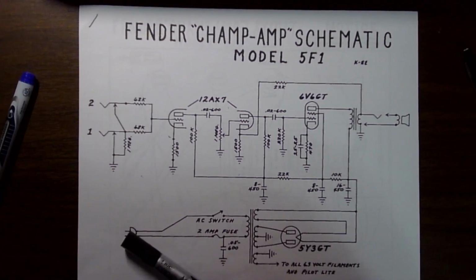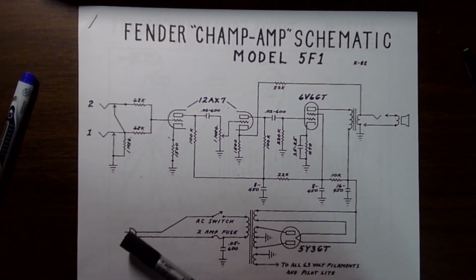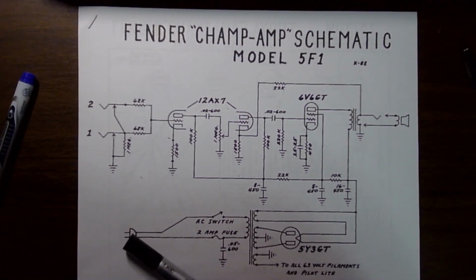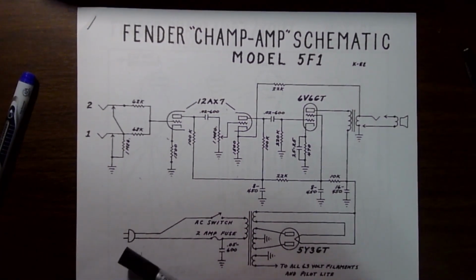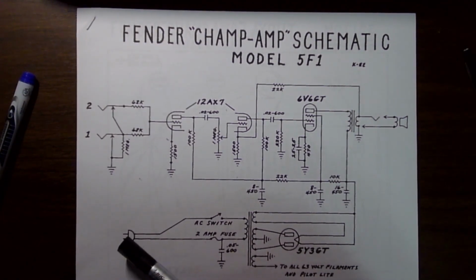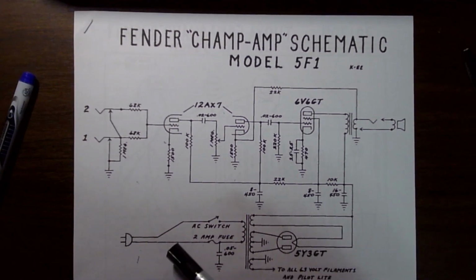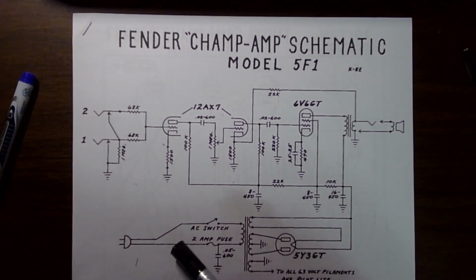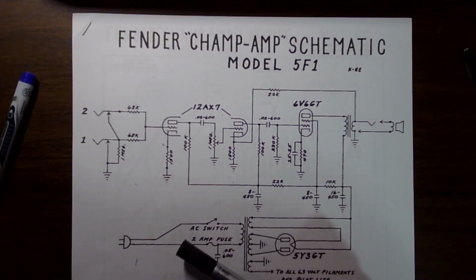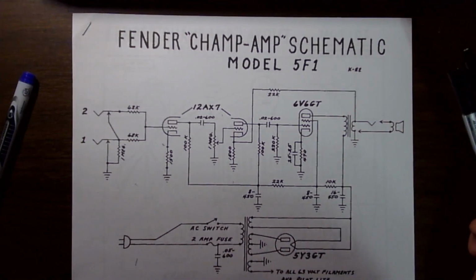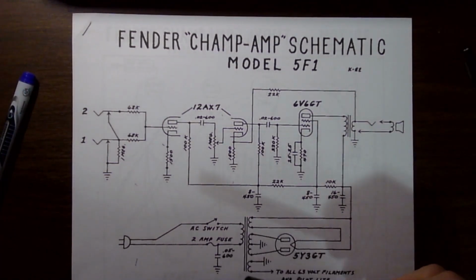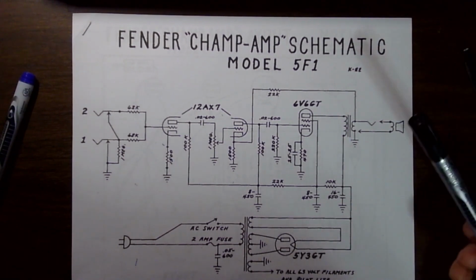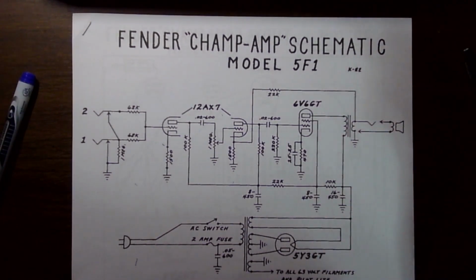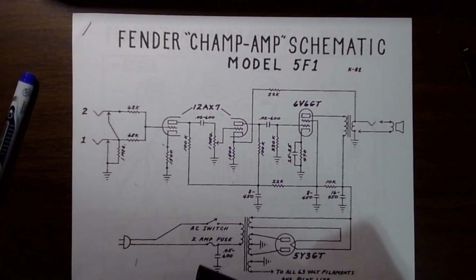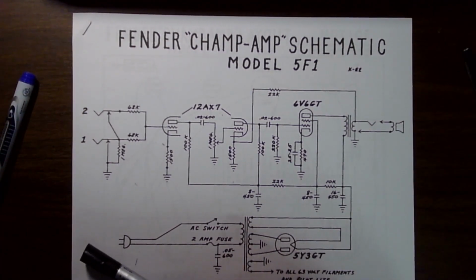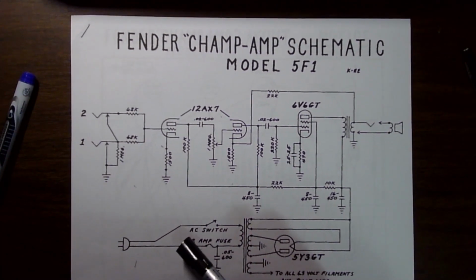The neutral or common, the white wire, the white blade on the plug, is connected to earth ground. So on this part of the circuit there's an earth ground, and if you touch this thing and you have no shoes and you are in like 1 inch of water, the juice is gonna go through you, so that's not good. That's why you put an isolation transformer here, so that there's no earth ground there anymore.